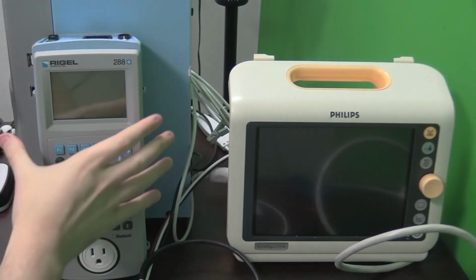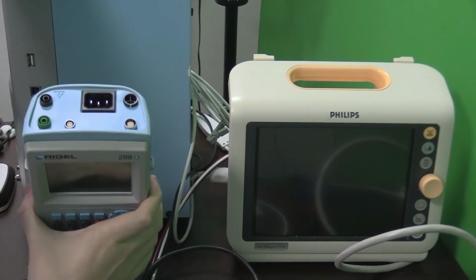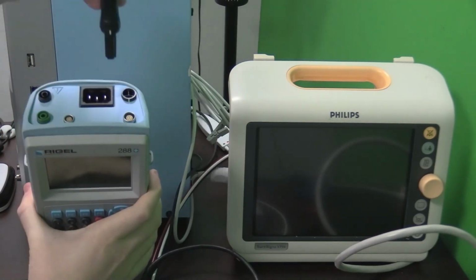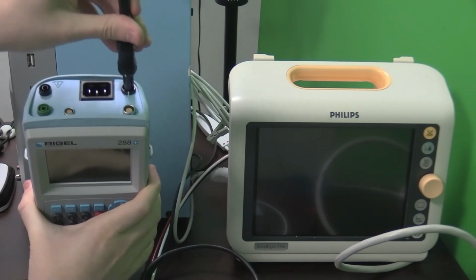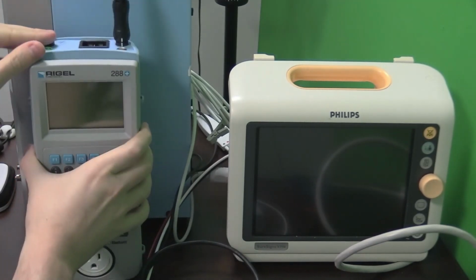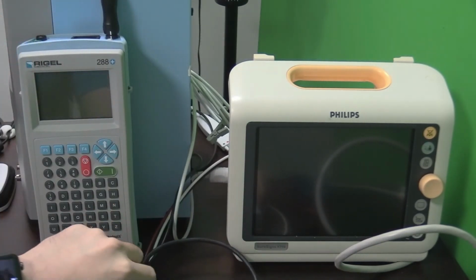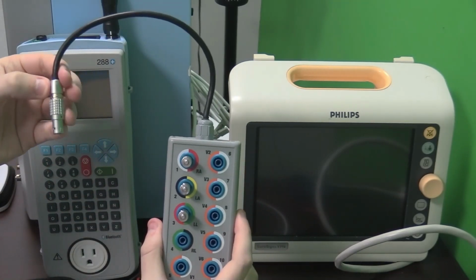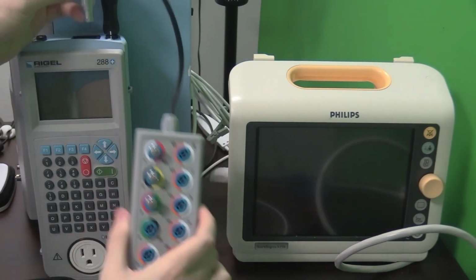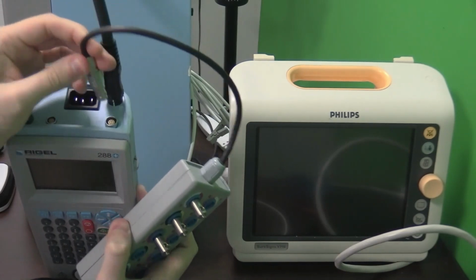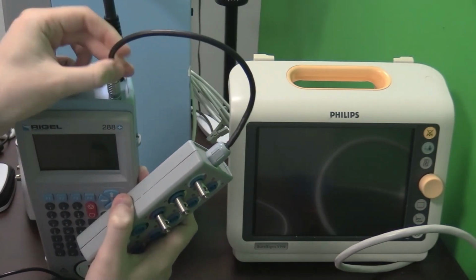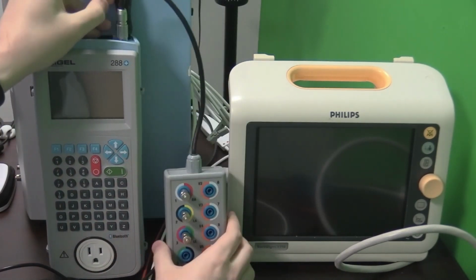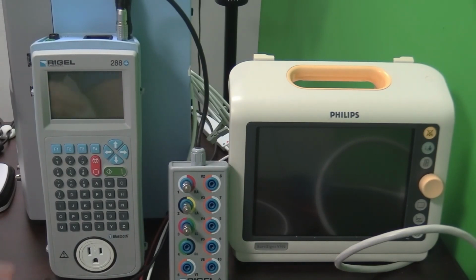Now before we run any tests, we need to hook up the device. So first you're going to take your power cord and you're going to plug that into the back of the device, ensuring that the two white lines connect with each other. Next, you're going to take your applied parts box. There's a little red dot on the applied parts connector that's going to face forward, similar to the white lines on the power box.